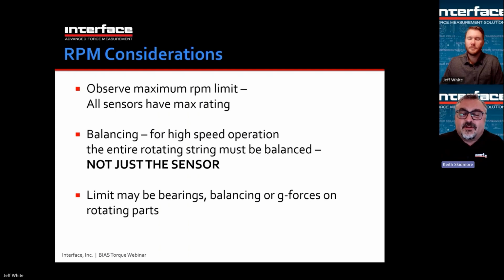All right, all sensors will have a maximum RPM rating. If they're bearing style sensors, sometimes the bearings are the limitation. Also, some rotating electronics due to G-forces and things. As the capacities go up on the sensor, typically their diameter goes up, and that means the bearings diameter goes up, and also the radius of the rotating electronics gets greater. So in almost all cases, you'll find that there are RPM ratings of sensors, and those RPM maximum ratings decrease as the capacity goes up.